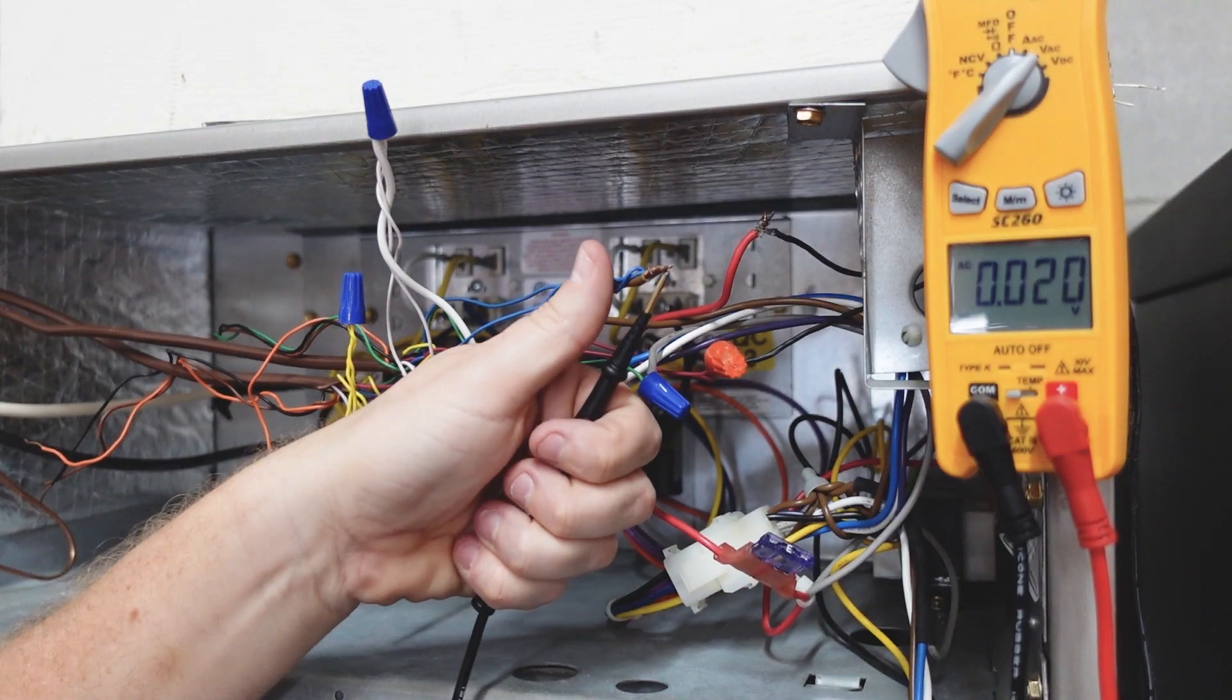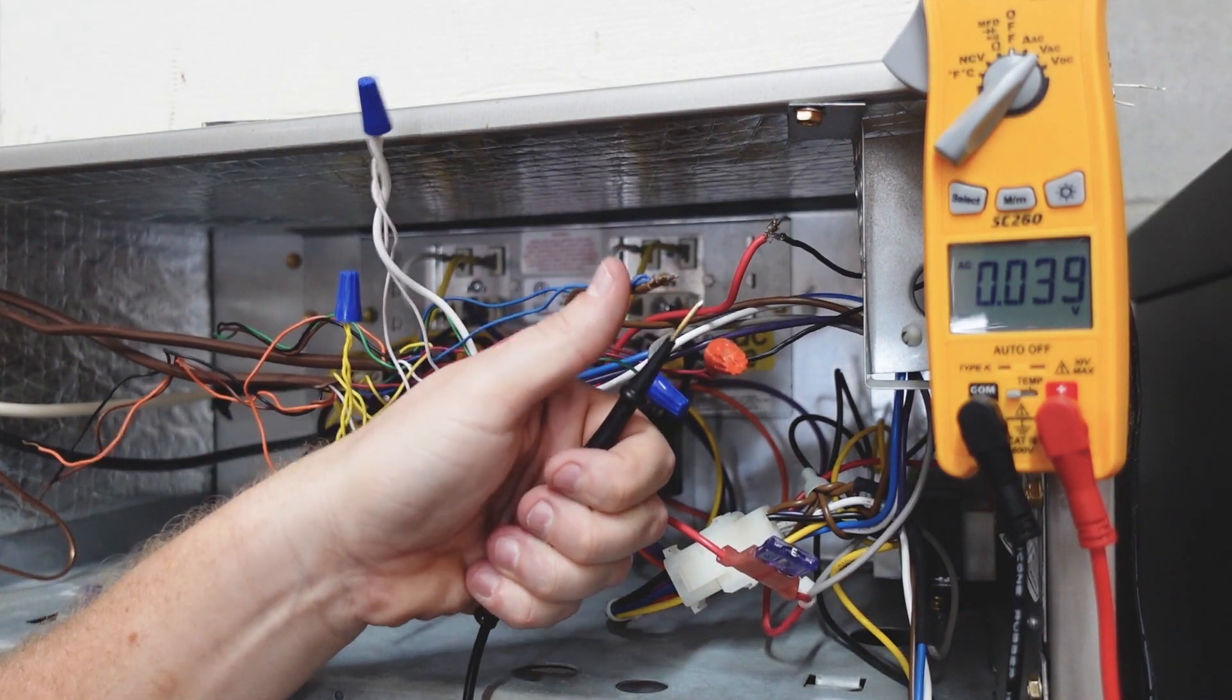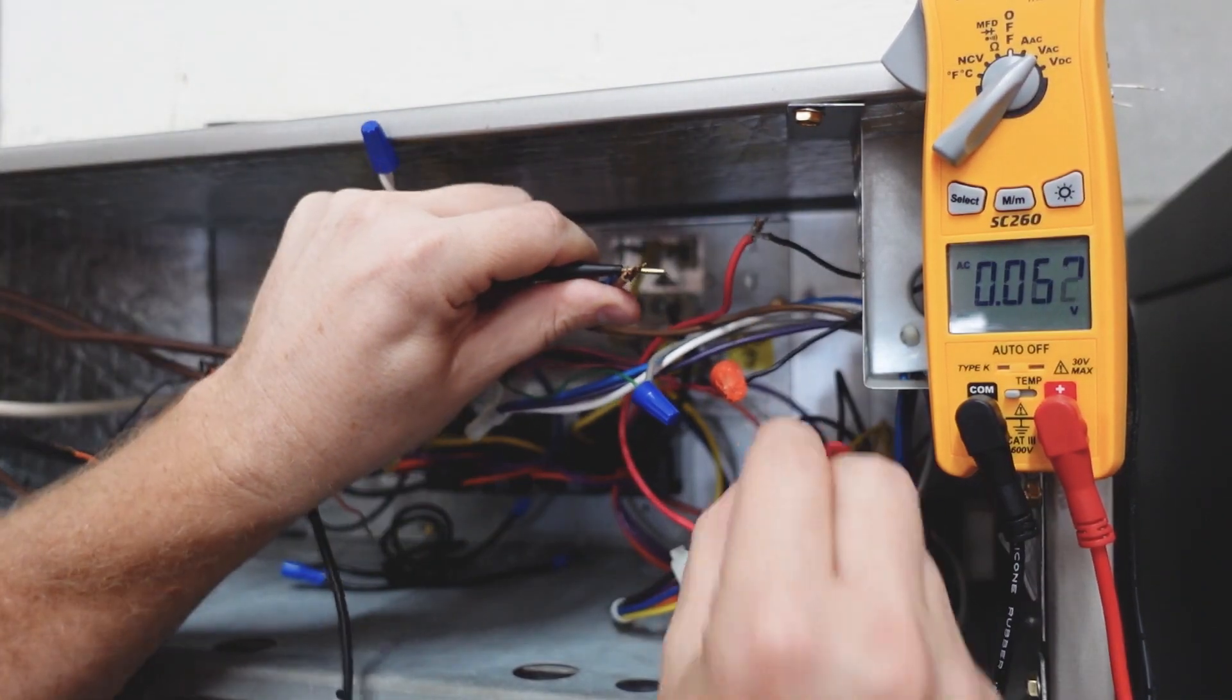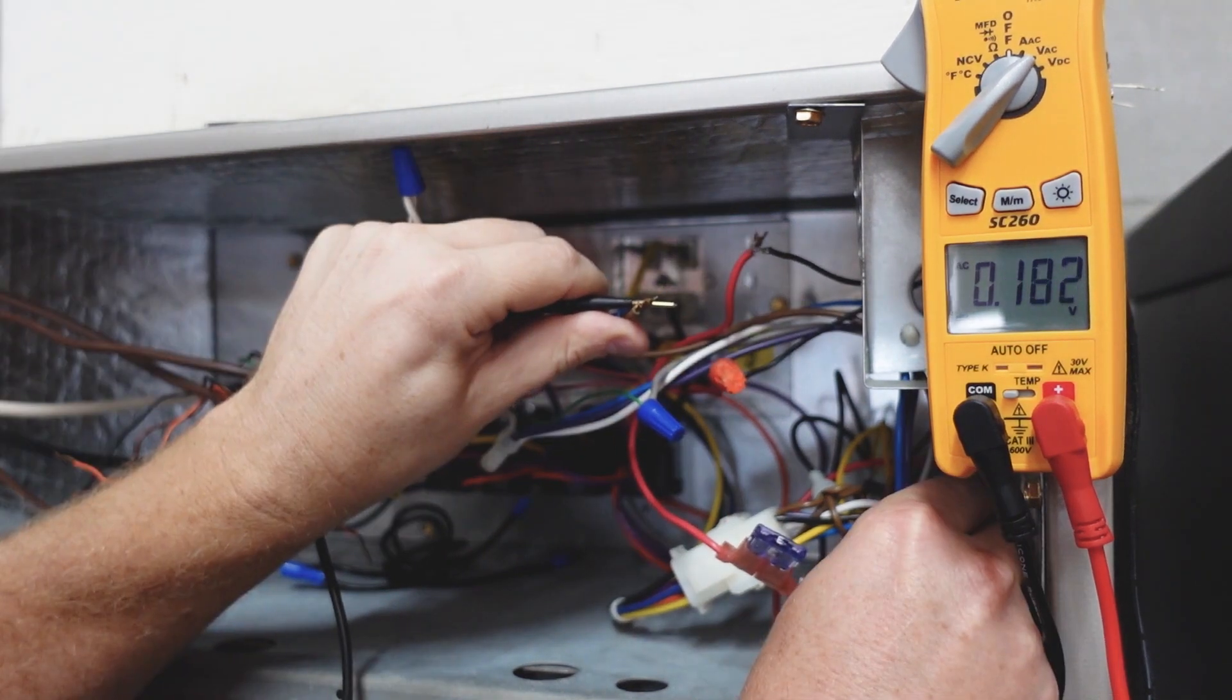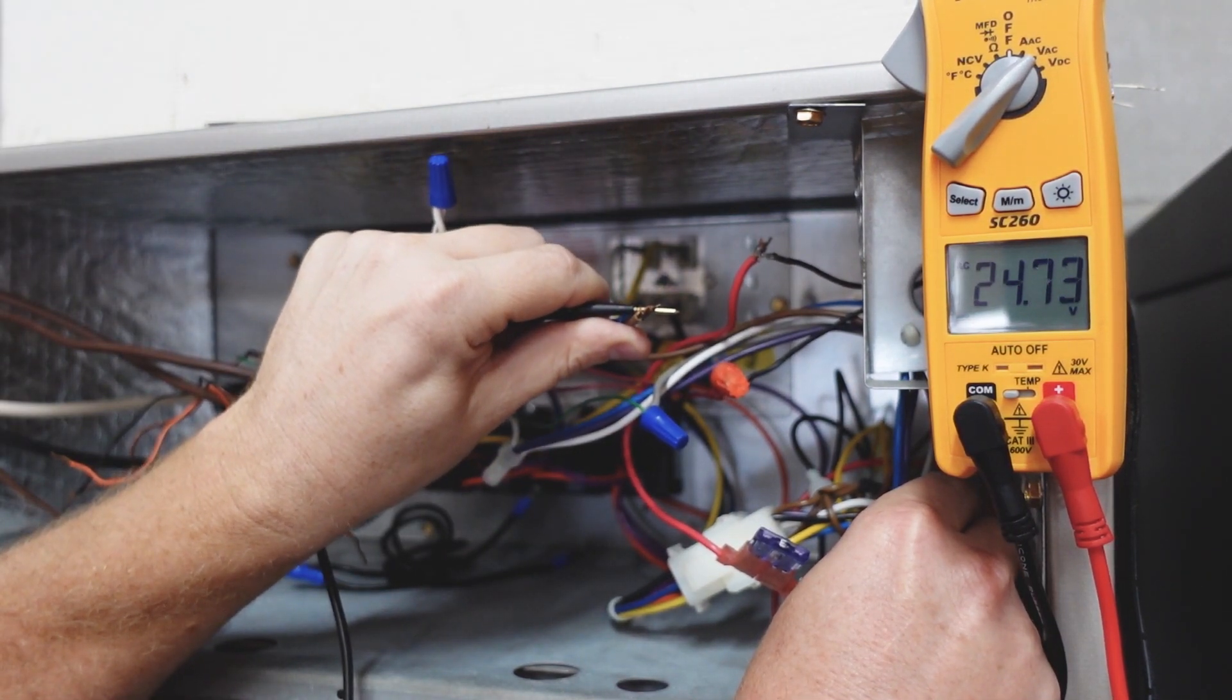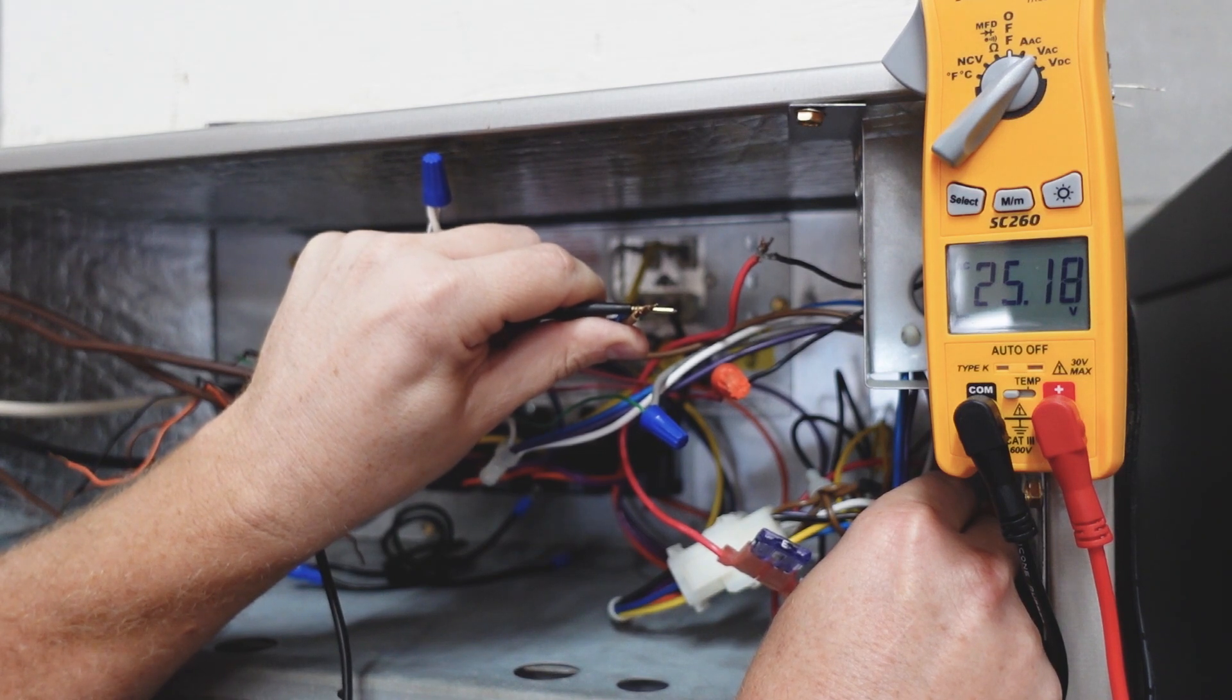So let's just see what we have. I measure from brown, which is common, coming from the transformer. And I go all the way back in and I measure from our hot, getting good access points is the tricky part for this test. So now I'm going directly from red to common on the transformer and I have 25 volts.